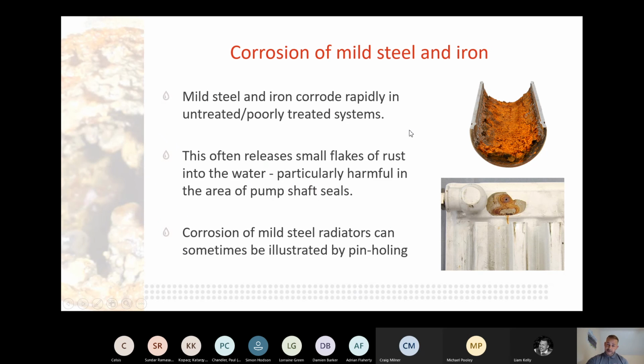Again, relating to what Craig said about the corrosion cell, mild steel and iron can corrode in untreated and poorly treated systems. It will often result in small flakes of rust entering the stream, which can lead to erosion, sludge, bake-on deposits, pump shaft seals as well. This can cause problems, certainly with the flakes.